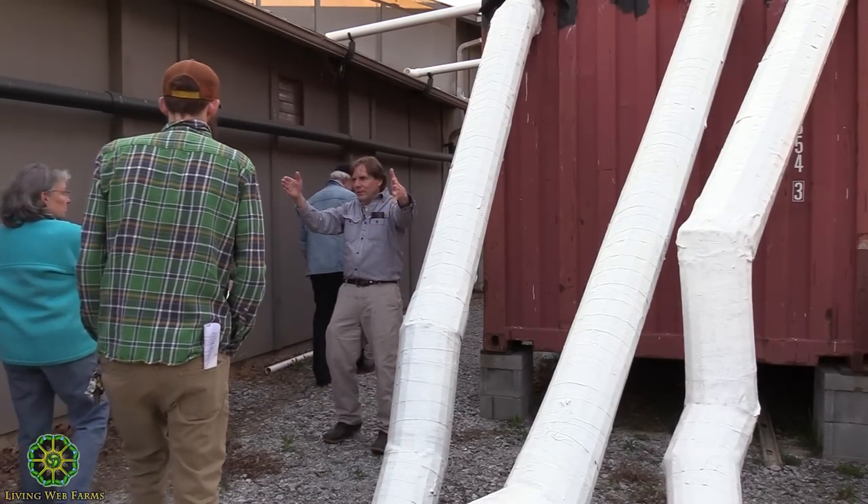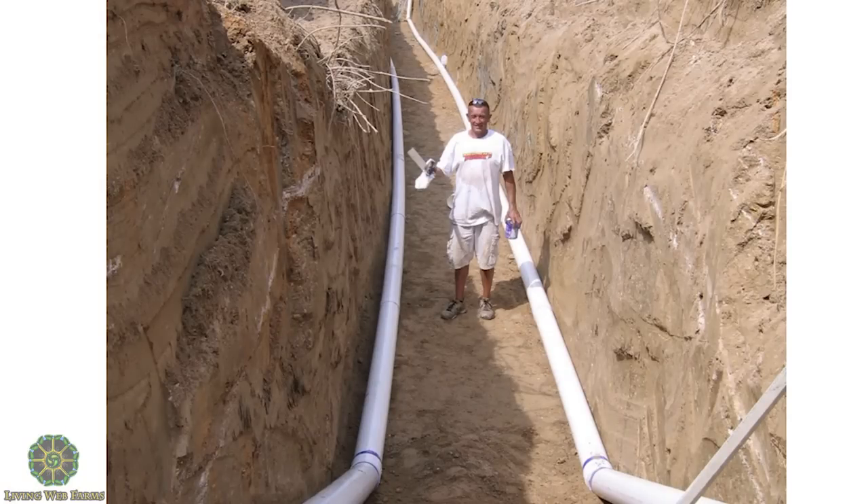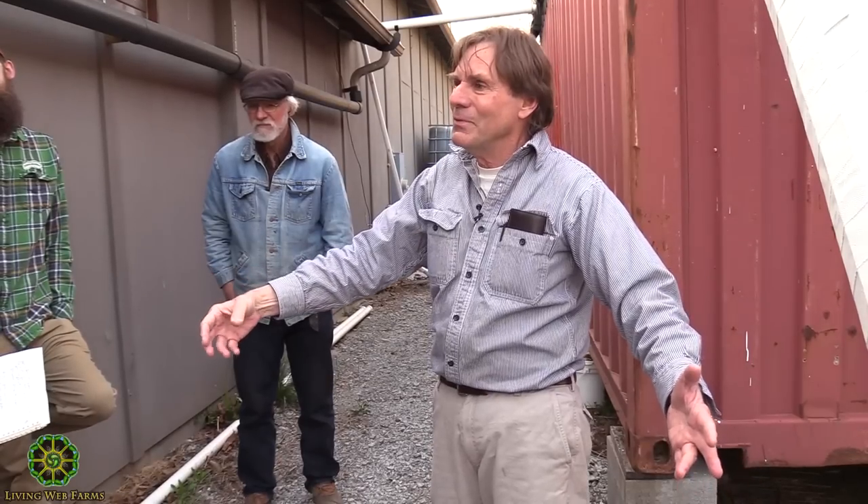I had a very limited access and site situation — five feet between pipes, a certain depth, and a certain length were fixed constraints. If I had had the option, I probably would have put a shorter run with more pipes, or bigger pipes, if cost permitted. If you have more pipes you can do less distance. The five feet between pipes is to equilibrate the temperature — there's a certain amount of storage in the soil, and it's being sucked out constantly like a bank account. If you had only a foot between two or three pipes working, on a hot day when you're asking for more cooling it's going to run out of cold.